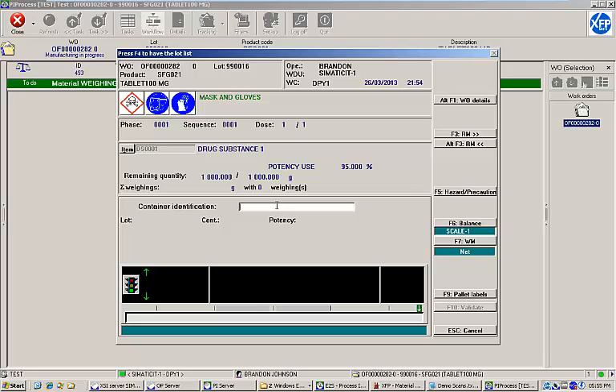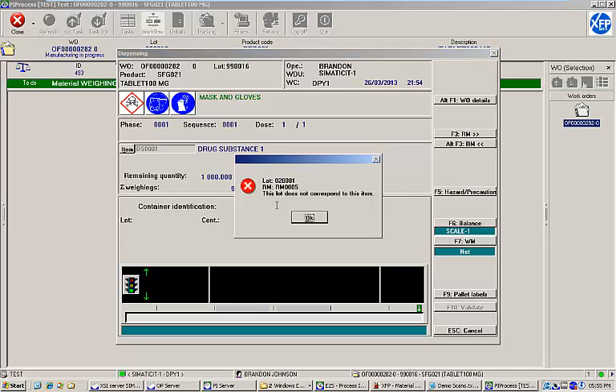Note that if I try to identify an expired lot, the MES will not allow me to continue. Similarly, if a lot of the wrong material is scanned, an error message is shown and the operator cannot continue. The controls and features of the weighing module ensure that the correct quantities of the correct materials are weighed and tracked within the EBR.